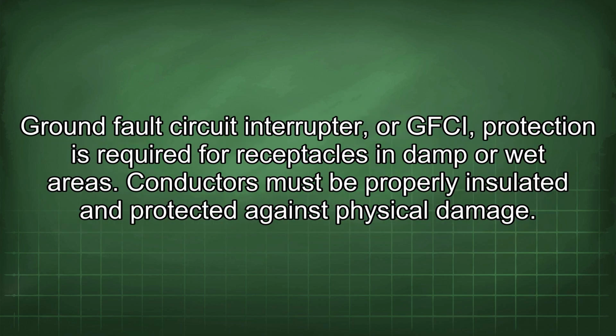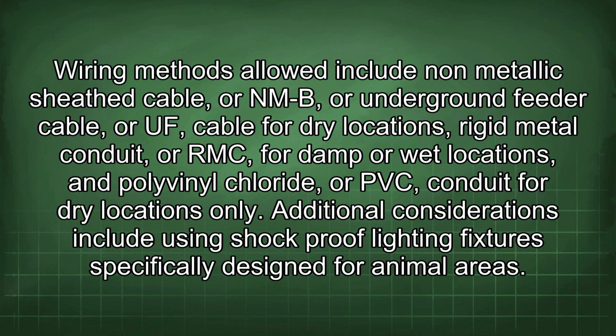Ground fault circuit interrupter, or GFCI, protection is required for receptacles in damp or wet areas. Conductors must be properly insulated and protected against physical damage. Wiring methods allowed include non-metallic sheathed cable, or NMB, or underground feeder cable, or UF cable, for dry locations, rigid metal conduit, or RMC, for damp or wet locations, and polyvinyl chloride, or PVC, conduit for dry locations only.